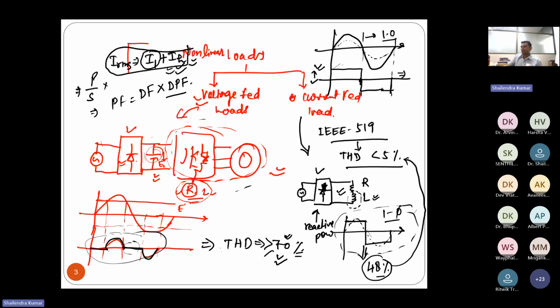So suppose a transformer is rated for 6 ampere and you are getting 0.5 ampere from this harmonic current, total current would be 6.5 ampere. It will increase the total RMS current through the transformer. And if total RMS current is increased, what about the heating losses or I square R losses? There is a significant increase in the heating of the transformer as well as the losses in the transformer. So we need to address this kind of issue over here.